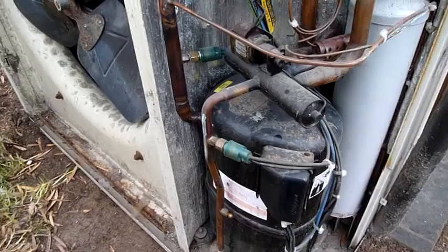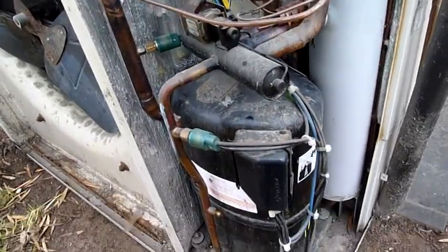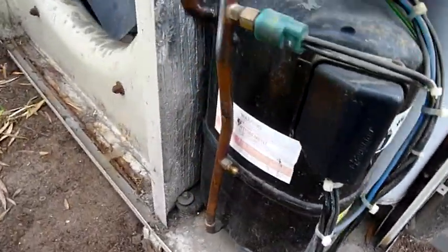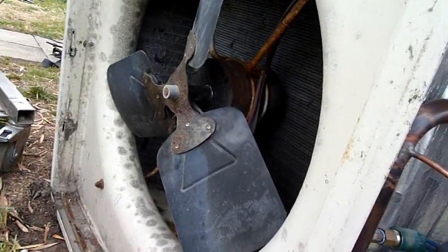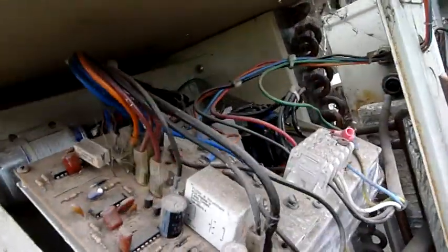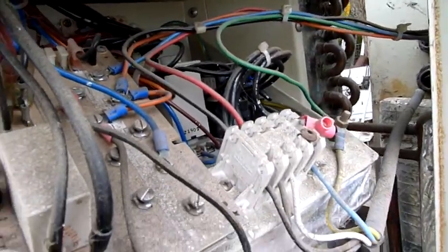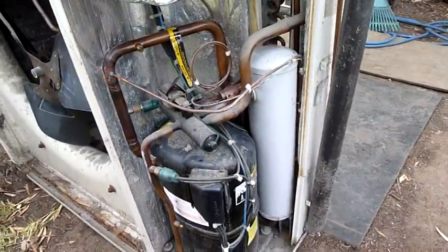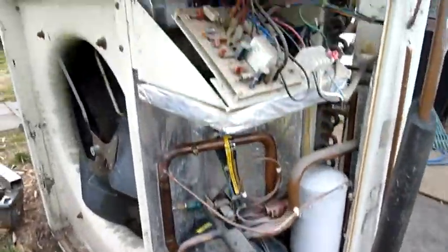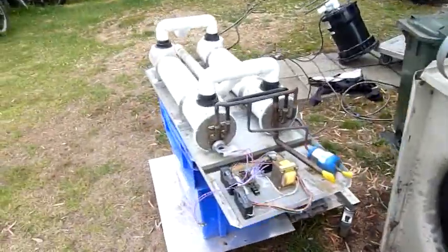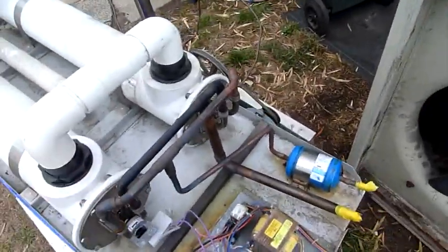Bit of tubing to keep. There's some nice copper in there for odd jobs. Again, pressure sensors and things like that. The TX valve sensing bulb coming straight off the accumulator. Single phase fan, it's very old and degraded. Won't be keeping any of that. I'll keep the timer and the plug base there, octal socket. The solid state time delay relay there. There's some good stuff. Anyway, I'll keep stripping it down. And that's the other one. I'll keep all that on the base. It's all one unit.